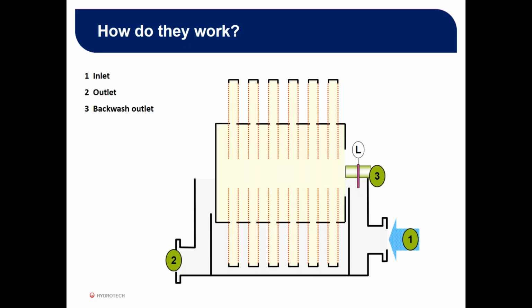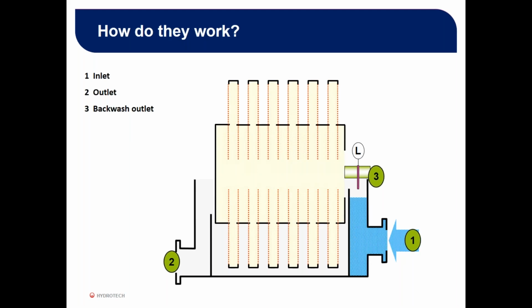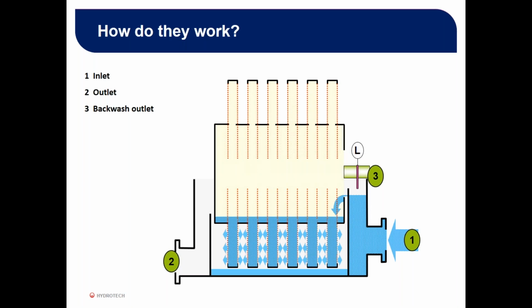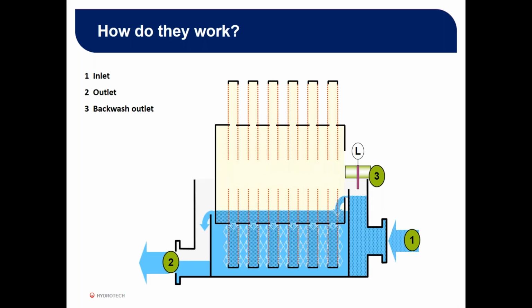So how does a disc filter work? You see at the bottom right of your screen there, the influent comes in the influent chamber, fills it up, and overflows into the discs. The Hydrotech disc filter is an inside-out filter. So the influent water, the raw water, flows into the discs and then out both sides of the disc into the effluent tank. Both sides of the disc are covered with the filter cloth, which is permeable, and the solids are kept within the disc. As the effluent tank fills from the water going through the disc, it overflows into the effluent chamber and then out by gravity. The whole system is operated by gravity.